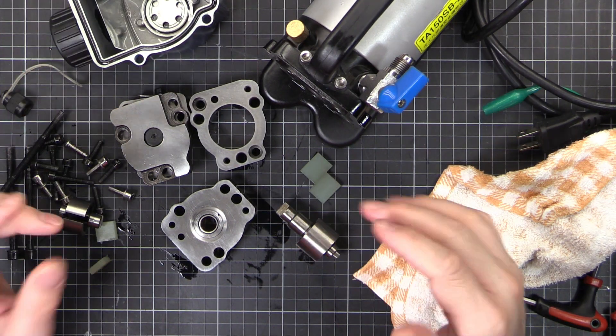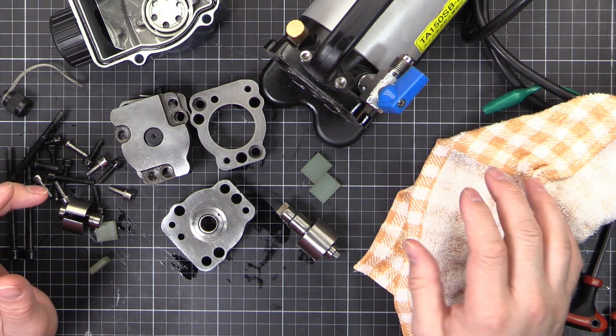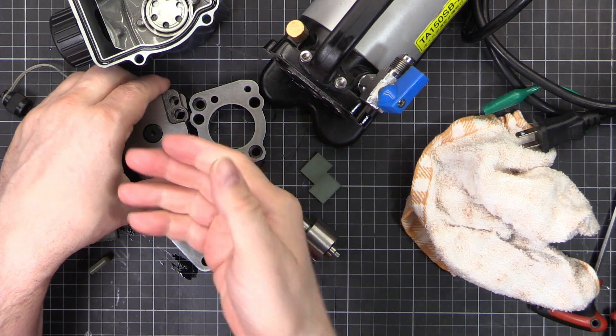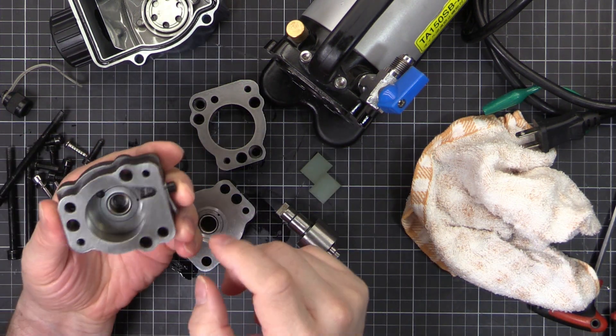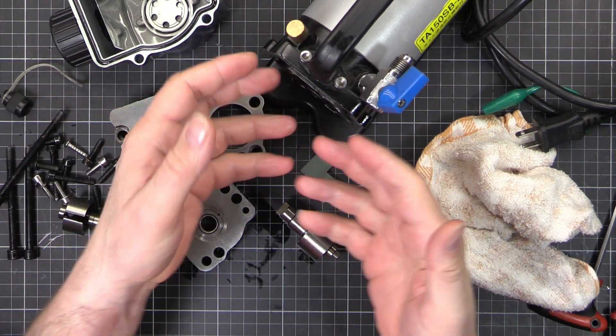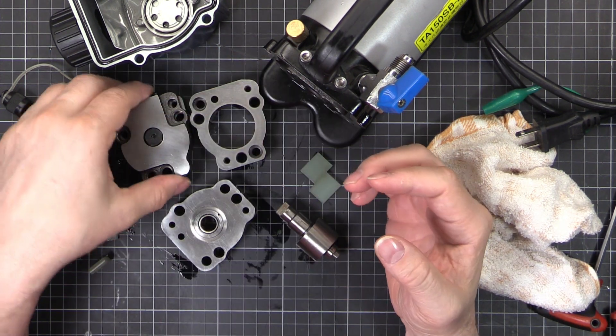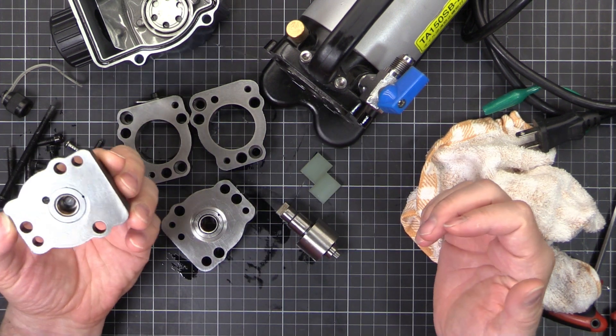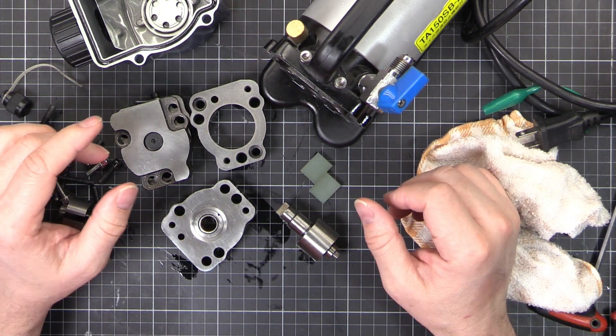Give it a clean out and get it back into service. But when I pulled it out, I noticed that because of the moisture that goes through it, the cast iron parts were getting a little bit rusty. So I thought I'll just take the sections of the pump apart and give them a clean up and put it back together. How hard can it be?